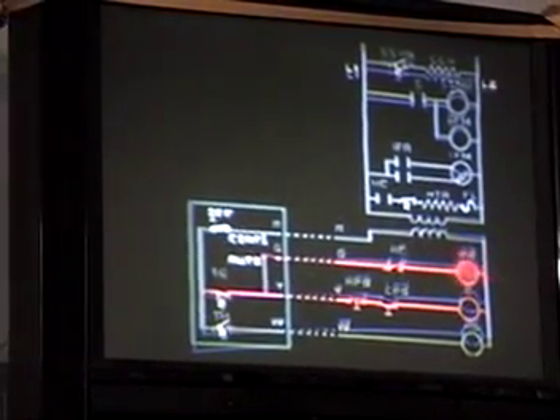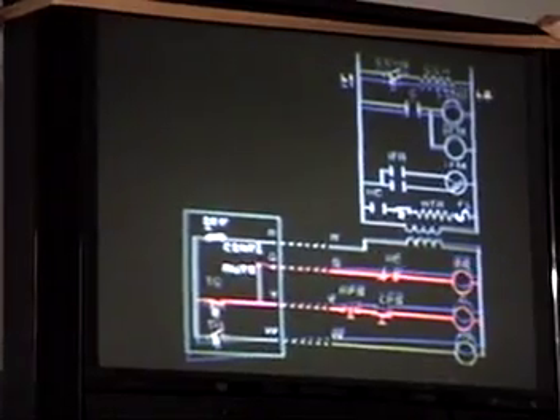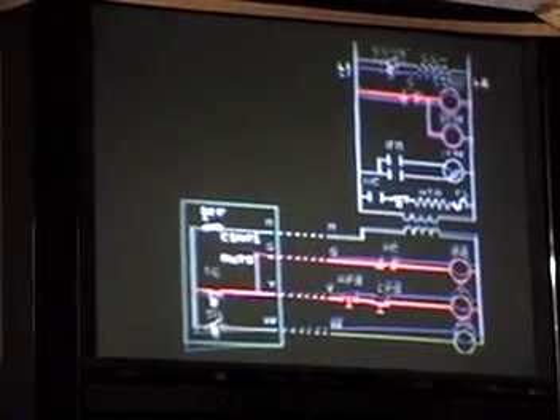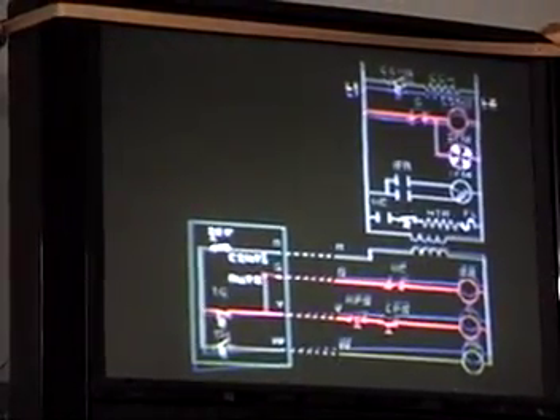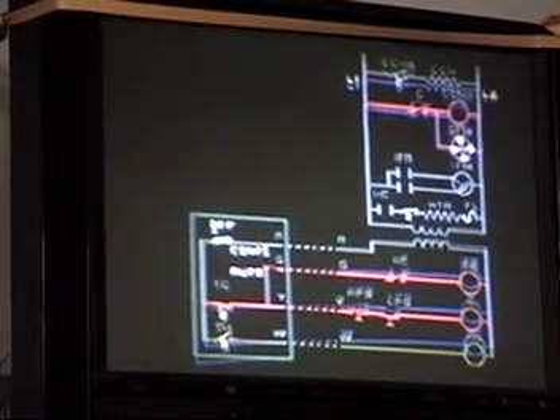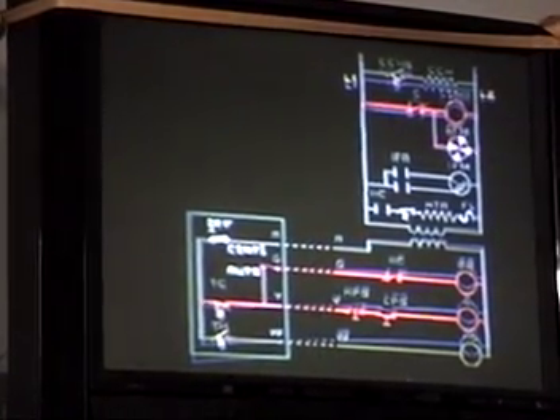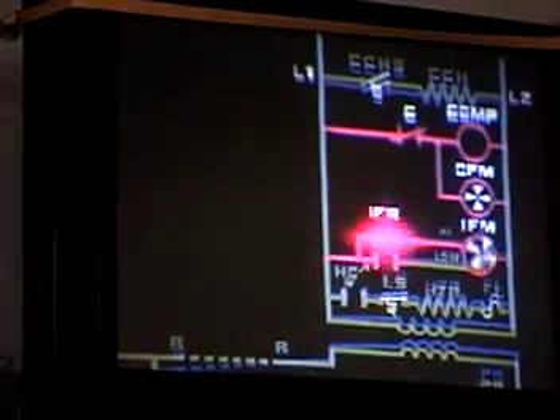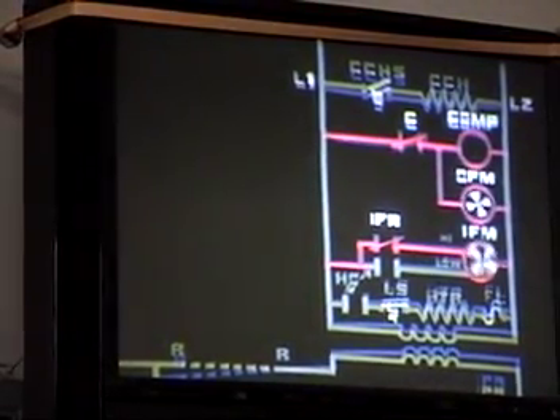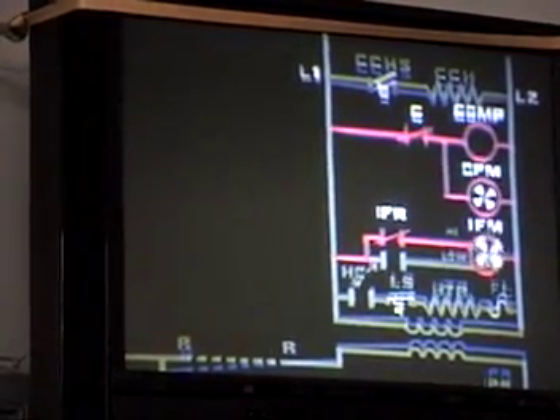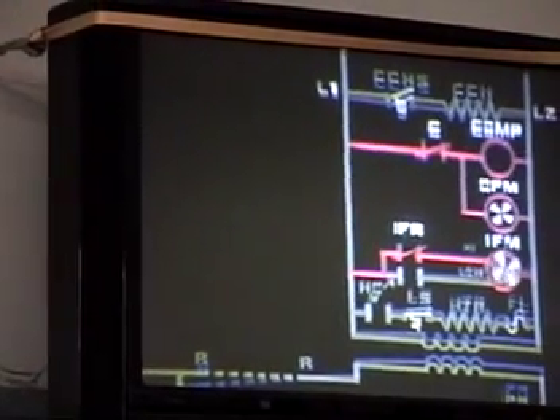The energized contactor coil closes the contacts in the power circuit and starts the compressor and the outdoor fan motor, which is in parallel with the compressor. The indoor fan relay contacts also close, and this starts the indoor fan motor. It runs at high speed because we need higher air flow in cooling operation.